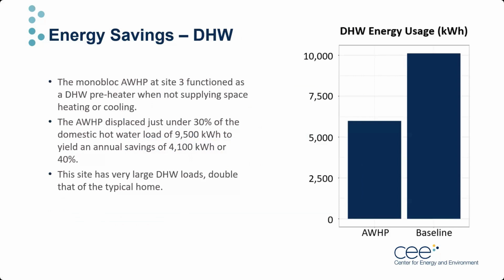And here are the energy savings associated with domestic hot water only. And while this looks good as well, there are a few caveats here. As we mentioned earlier, the system at Site 3 only provided DHW when it was not responding to a space conditioning call, so domestic hot water preheating was not prioritized. This home also had an abnormally large need for water heating, about double the typical single-family home in our state. Still, the air-to-water heat pump displaced just under 30% of the load and produced an annual energy savings of about 40%, or 4,100 kilowatt hours. While the large absolute savings are attributable to the high load, it is likely that percentage savings will be larger at sites with more moderate hot water consumption. Next slide.